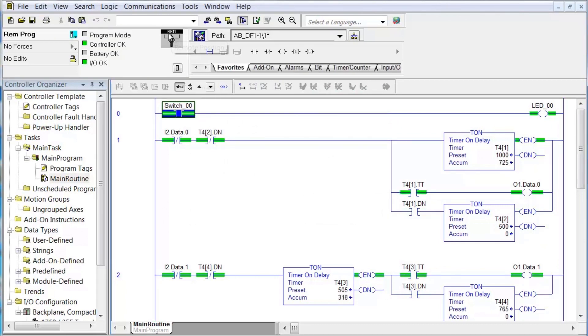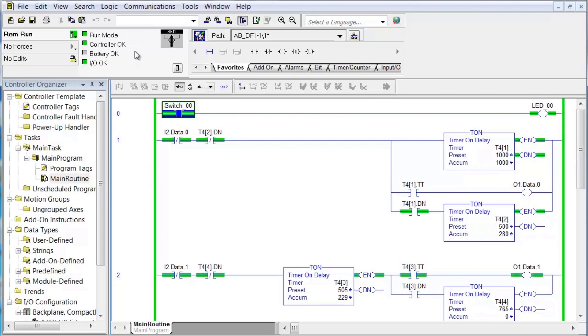Pay attention to this key switch symbol, the color, and the text. As I use the key switch, notice that rotating it over to program puts you in program mode. Back to the center position the key switch says remote but you're in remote program. Switching to the other direction is run mode, but we want to switch back to the remote position. The key switch should always be left in the center position so you have remote access to the processor. In most manufacturing facilities they pull the key switch out, and the only way to change mode is to go through the program and click on the box here and change it to whatever mode you want.